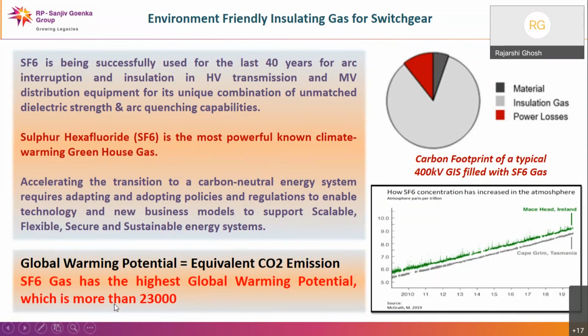You can see SF6 has almost 23,000 times more global warming potential, GWP, than CO2 itself. If CO2 is 1, then SF6 is 23,000 or more. Here you can see two pictures which I have taken from the internet. For a 400 kV GIS filled with SF6 gas, the major part of the carbon footprint, more than 80%, is due to the presence of SF6 inside the panel. The rest of the entire material accounts for only about 20%. So SF6 has a huge global warming potential, which needs to be reduced.